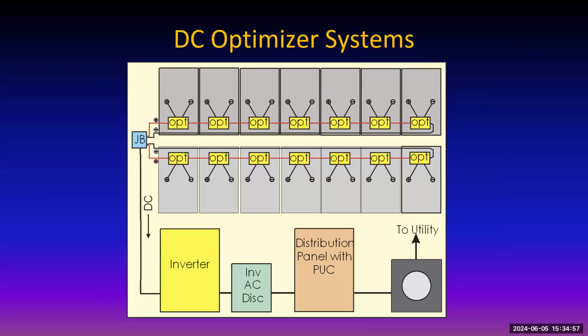Notice the difference. Optimizers are DC to DC converters. DC in, DC out. Notice they are connected in series. And the nice thing about an optimizer, the reason it's called an optimizer, is because it has its own maximum power point tracking, which means it will make sure that module is operating at maximum power. It adjusts its voltage and current such that its current will be exactly the same as the current on all the other optimizers in that circuit, but its voltage may be different.